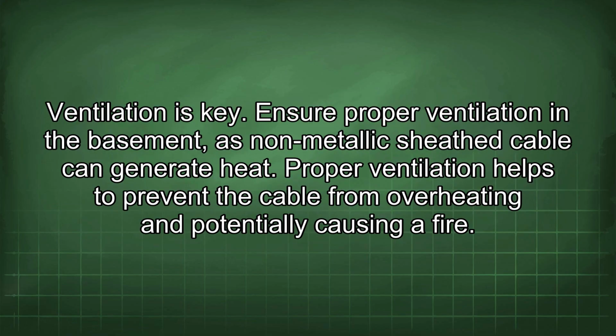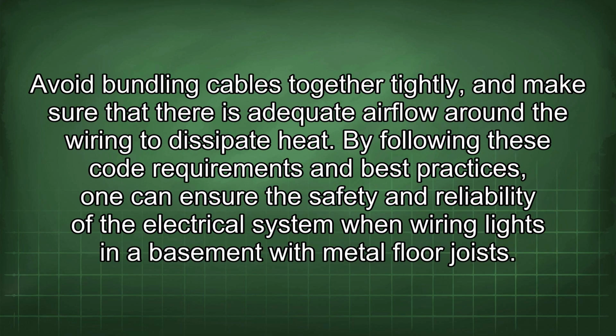Ventilation is key. Ensure proper ventilation in the basement, as non-metallic sheath cable can generate heat. Proper ventilation helps to prevent a cable from overheating and potentially causing a fire. Avoid bundling cables together tightly and make sure that there is adequate airflow around the wiring to dissipate heat. By following these code requirements and best practices, one can ensure the safety and reliability of the electrical system when wiring lights in a basement with metal floor joists.